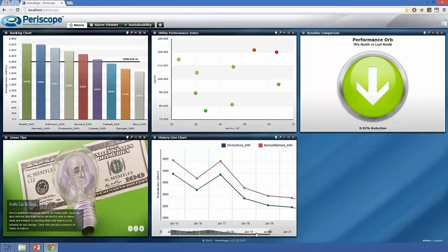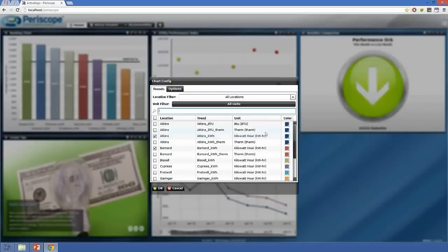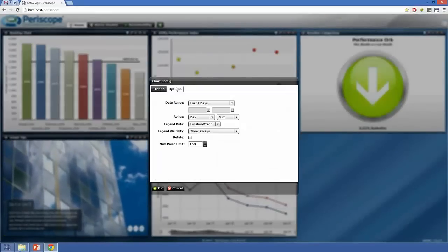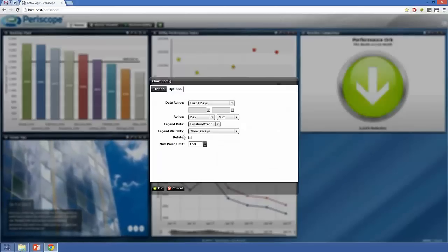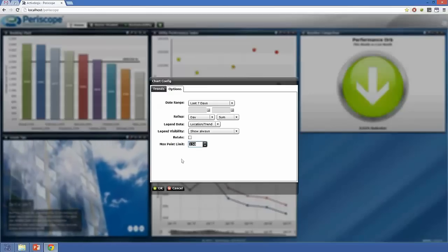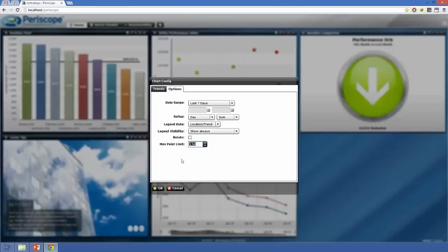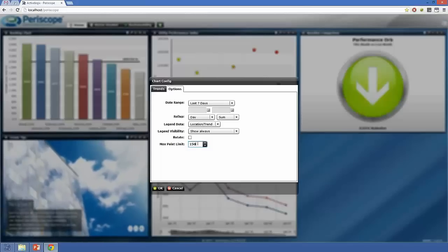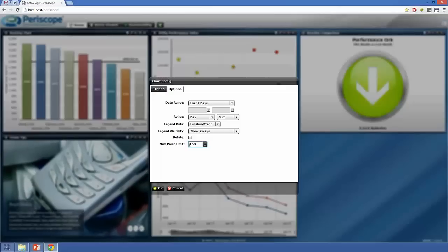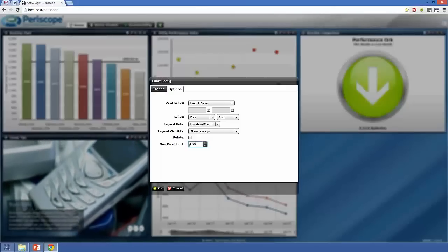One thing we found was that with a line chart, people will often try to trend hundreds of thousands of points, and we couldn't actually show all the data. If it's a slower machine, it might take a while. So this max point limit is going to automatically roll up if it exceeds that number of points. If we're looking at a year of data and they've got, let's say they're trending at 15 minutes, that's going to be more than 150 points. So it's going to try to roll up that data to the next level up, which could be days. If it's more than 150 days, it's going to try to roll it up to the next level, which is months.